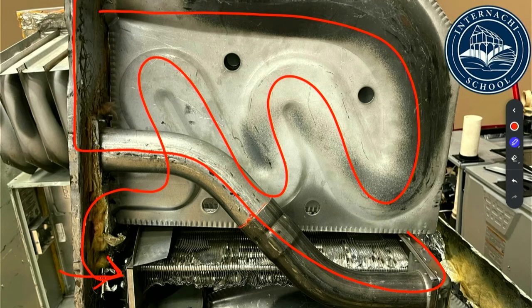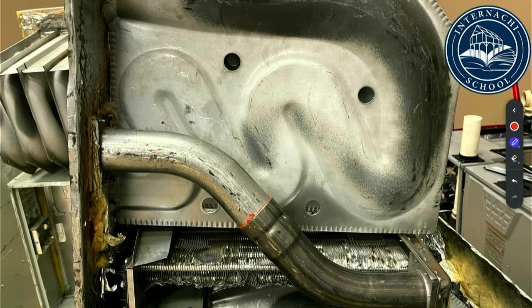If you take a close look at this heat exchanger, here we're looking at one of those eyelets where they push the two together and they crimped it on top of each other. This one is good, but if you kind of get up close to the screen at this one, I don't know if you can see the separation between the two pieces inside that circle. But that whole circle is let loose, and now this thing is opened up. And usually what's going to happen, because outside we're high pressure, inside we're low pressure or negative, so typically you're going to have fresh air going in instead of the carbon monoxide coming out. But again, any opening like that is considered dangerous, and the heat exchanger needs to be replaced.